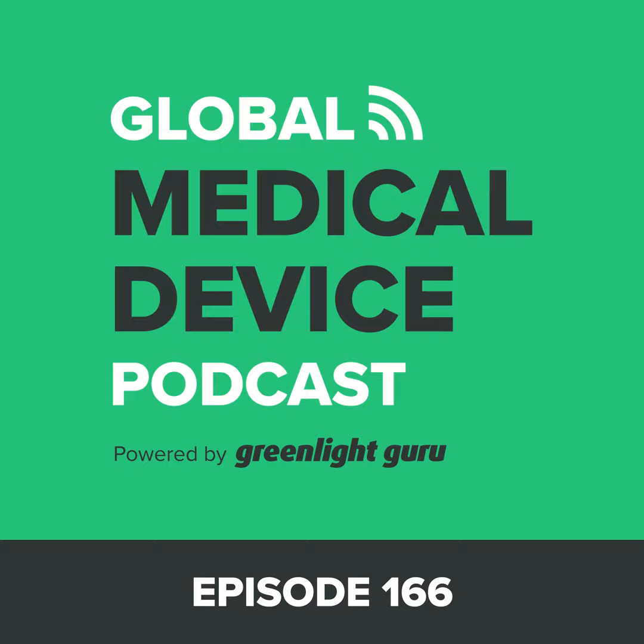Just to reiterate, folks, this is a topic that you need to address for any and all medical devices. Now, again, to be redundant from what I've said earlier, I get it. You may be developing a software as a medical device. Is biocompatibility applicable there? Probably not. But you can't just assume that you don't have to do anything. You still need to provide rationale, justification, and explanation as to why. I know it seems silly, but this is the expectation.